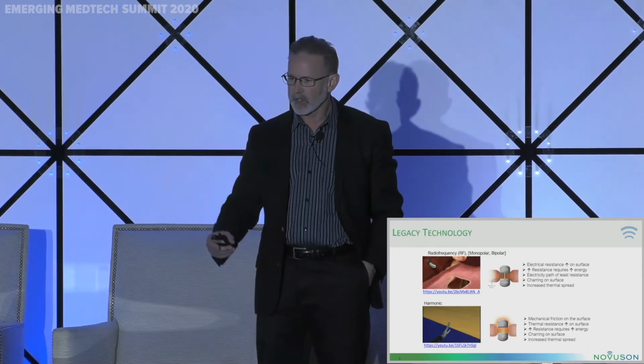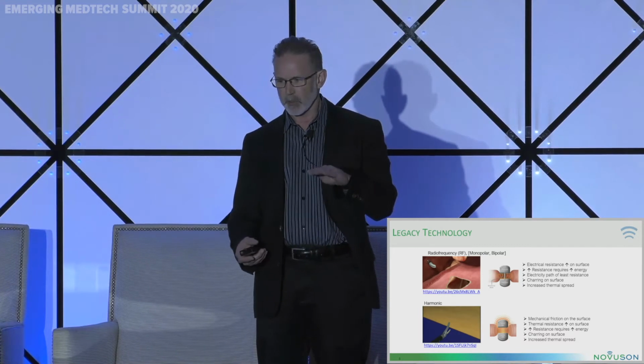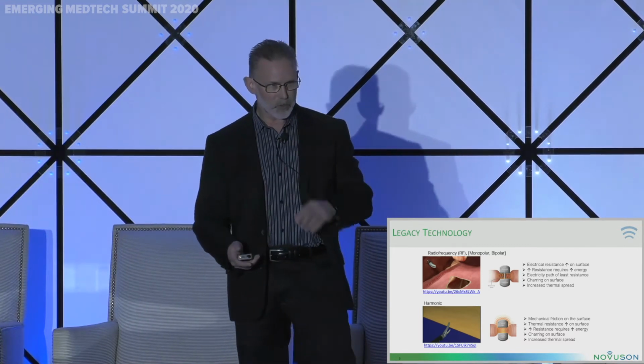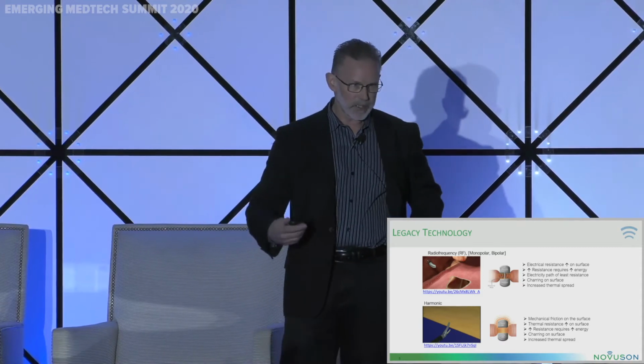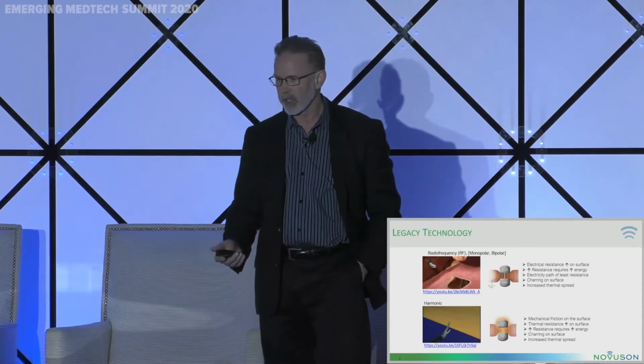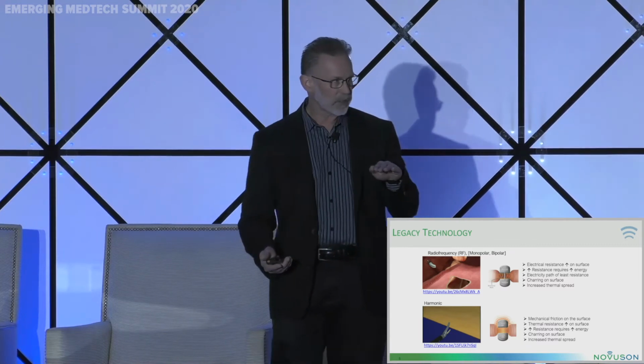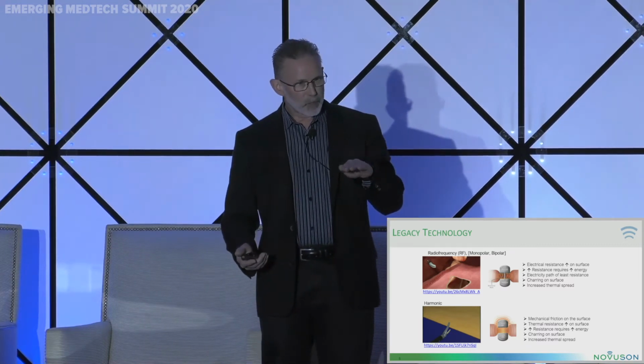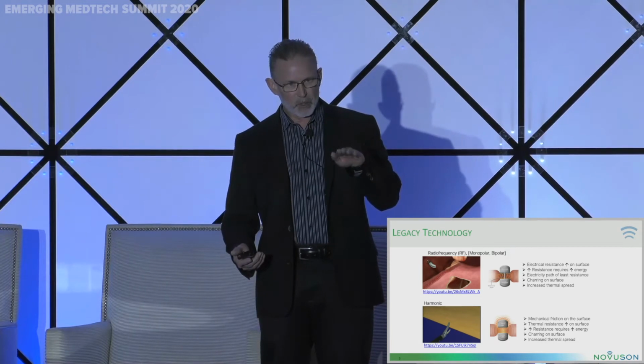The RF device takes and runs electricity from the top jaw to the bottom jaw, and that effectively cauterizes the tissue. They use a mechanical blade to cut the tissue. This is a sealer divider. The harmonic devices have a top blade that vibrates. It's a mechanical blade. It vibrates at ultrasonic speeds, and it uses friction to cauterize and cut through the tissue.